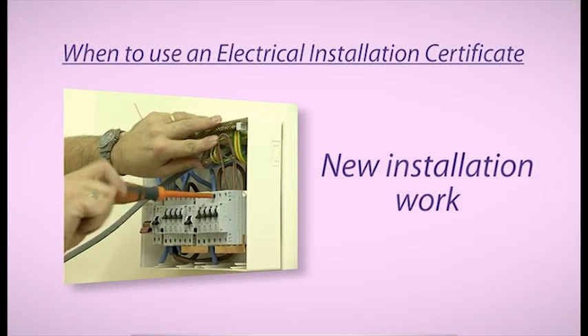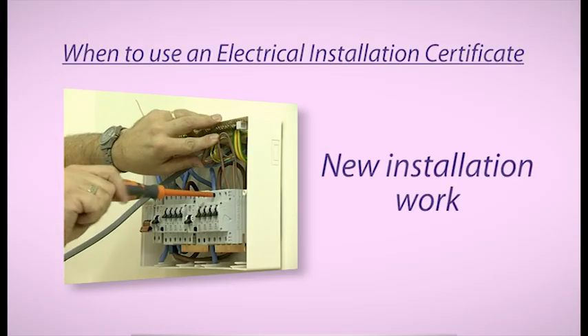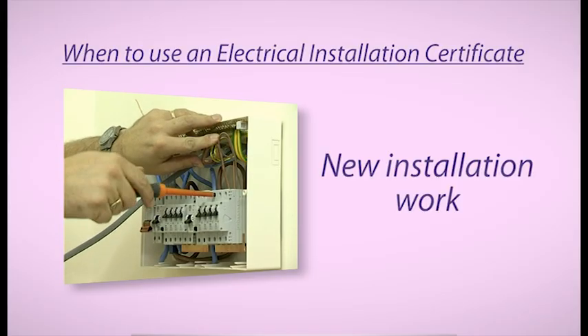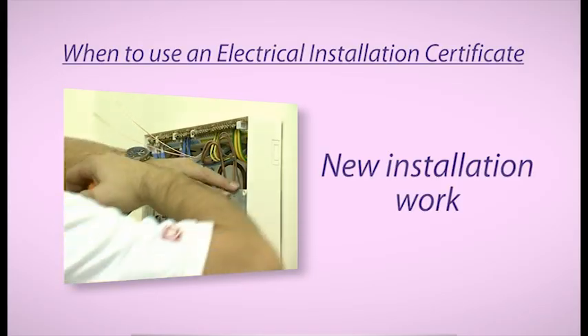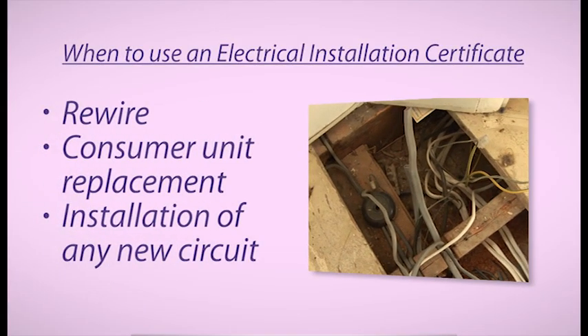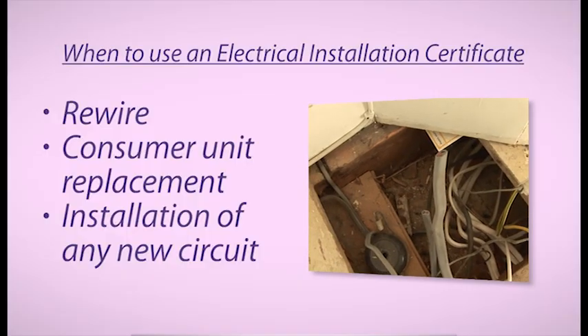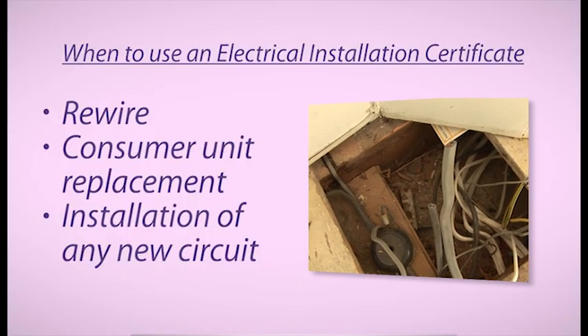Its most common use is for new installation work, for example on a new build project where the electrician will be confirming the standard of the work and the safety of the whole electrical installation. However, it could also be used for a rewire, a consumer unit replacement or the installation of any new circuit.